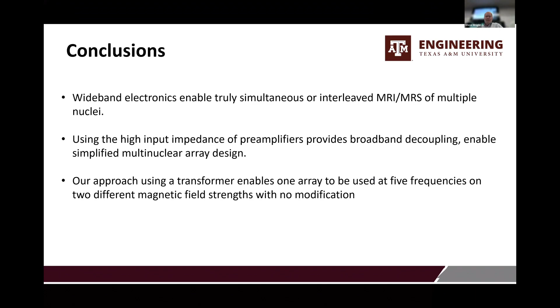And we have to pay for that magnet. We don't have to pay for ours. So we haven't gone back to use that. But the point is now we've tested the single coil at 5 different frequencies on 2 different magnets without retuning. And we think that's kind of useful. So the wideband electronics, we can now really do truly simultaneous or interleaved MRI, multiple nuclei. High impedance preamplifiers allow broadband decoupling. That's the challenge, is decoupling those elements so they work independently. So we're pretty happy with that.